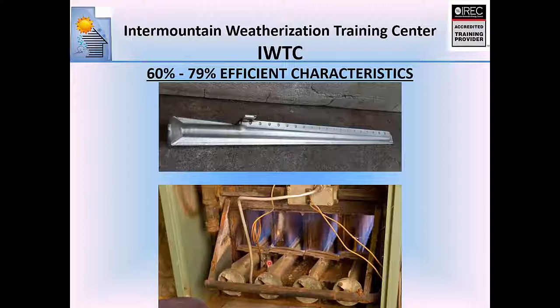Now, if you do a combustion analysis on this type of furnace, you'll probably get a combustion efficiency reading that's over 70%. And I often get phone calls: well, I'm on this 60% furnace, and the combustion analysis is 73%. How is that possible? Well, the reason this is rated at 60% efficiency is because of this standing pilot. You have this pilot that's always on, using gas, and the heat it produces is not being used to heat the house whenever the furnace is not running. So the manufacturer has to take into account the gas used versus the heat energy delivered to the house. And when you add up the heat energy lost because of just this little standing pilot, it causes the overall efficiency on this furnace to go down to around 60%.